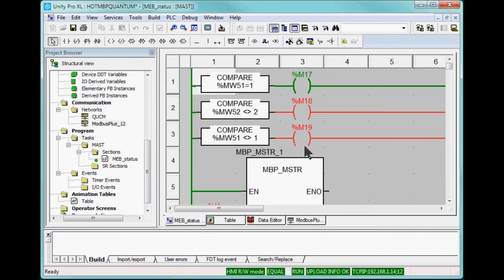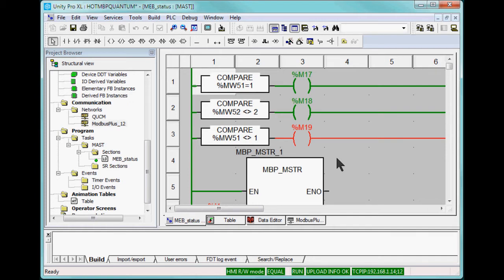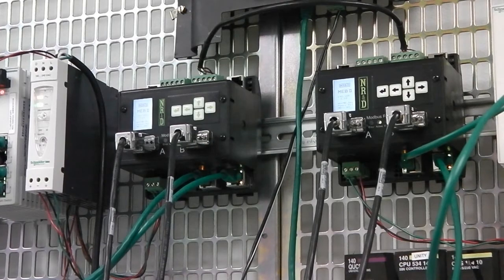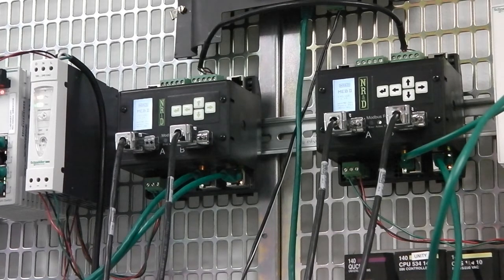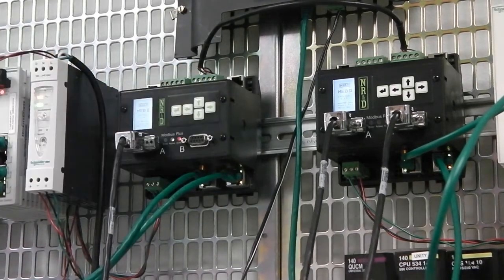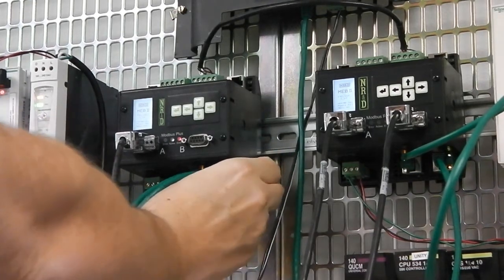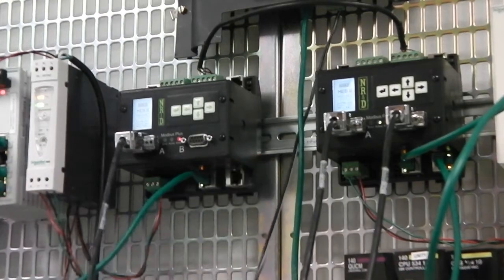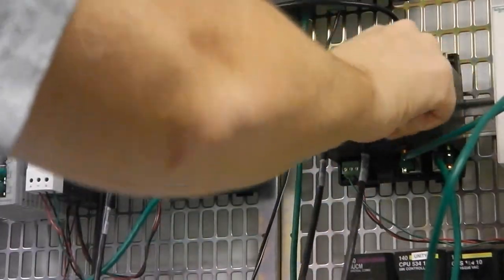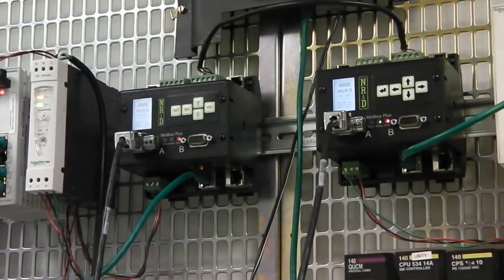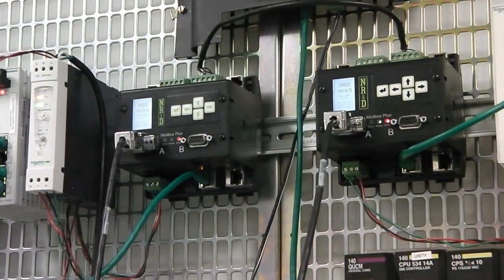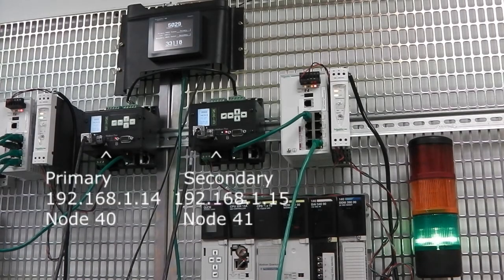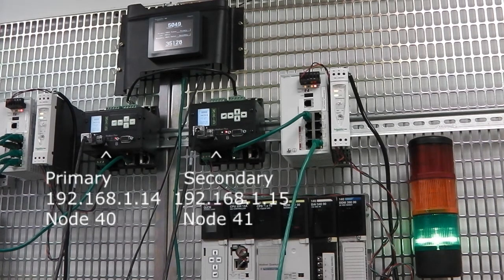The green light, controlled by the top rung, means that the primary is good. The yellow light, controlled by the second rung, means that there's some problem with the secondary. And the red light, controlled by the third rung, indicates that the primary is not working. At this point, the left MEB2 is the primary. Removing the Modbus Plus cable from the secondary turns on the yellow light.